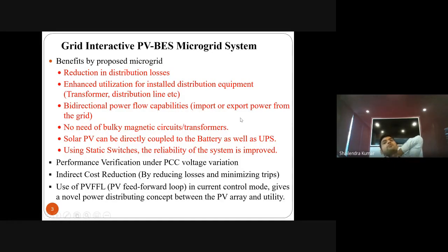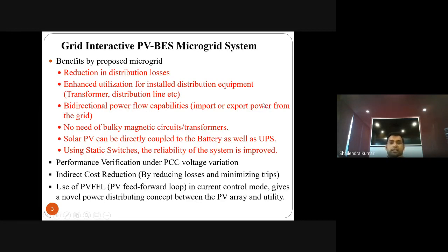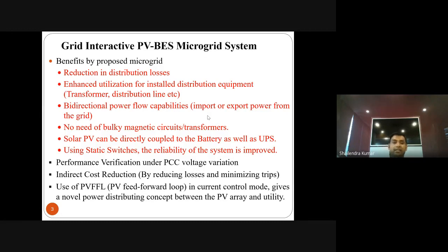The system operates autonomously — whether there is outage of PV array, grid, or battery, the control handles everything automatically. For battery energy storage, we use a bidirectional converter to control charging and discharging. Unlike conventional UPS systems that use high-frequency transformers to boost battery voltage to match the DC link, here we use a bidirectional converter for both boosting and bucking operation.